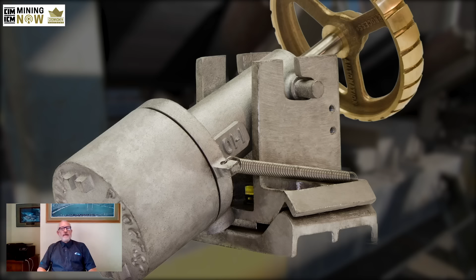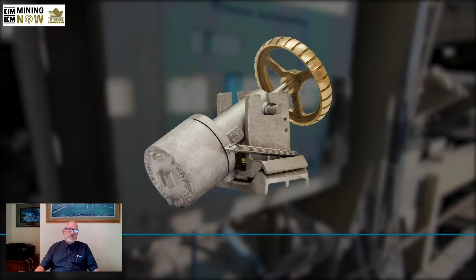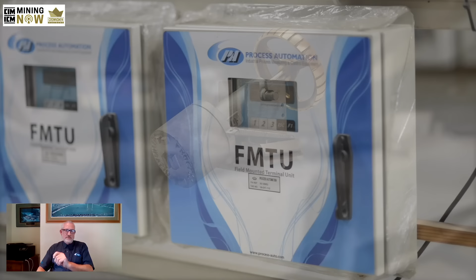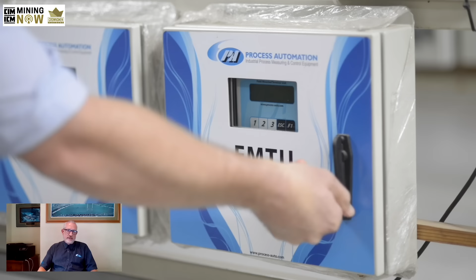So we said let's take the technology to the next level. Instead of just having a simple switch that tells you you're already in trouble or your belt has stopped, let's do one that tells you you've got a tendency towards slipping. So instead of a relay output, it gives you an analog output, 4 to 20 milliamp.